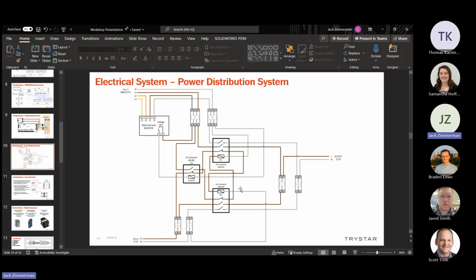Yeah, but generally, the system, I'm gonna call it, fails gracefully in that if you lose power to your controller, let's say your power supply dies, your contactors die, which are the same contactors we use in load banks. We're using well-known ABB contactors, trying to keep it well spec'd here, but the controller will go off and it will not change the state of the breakers. It'll go off. It might even kick up your backup generator, because it thinks it's off, and then it will keep your utility power online.